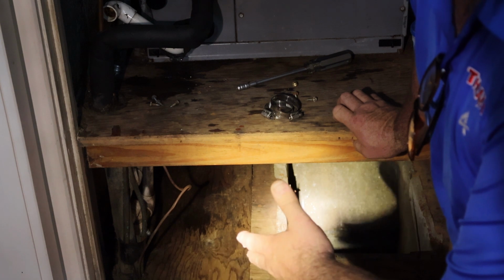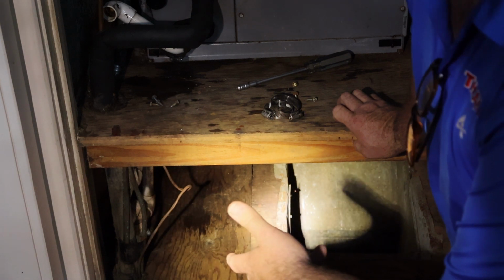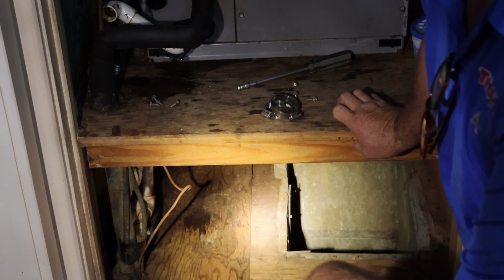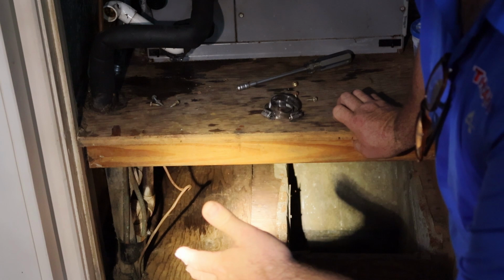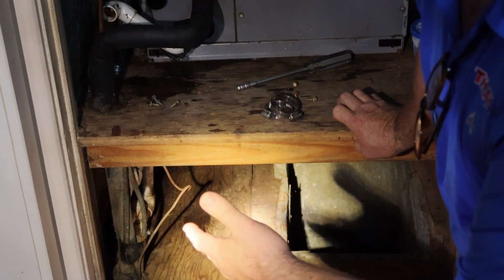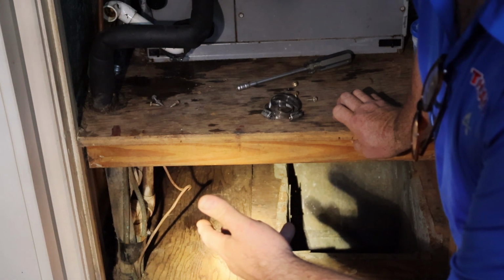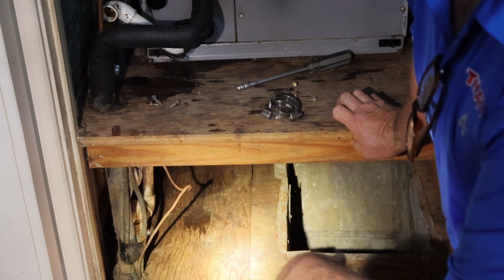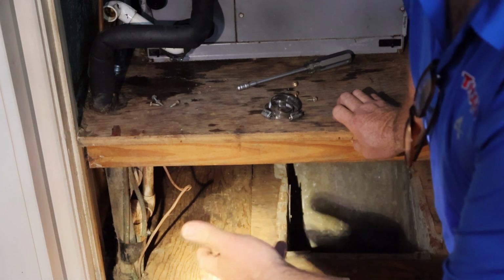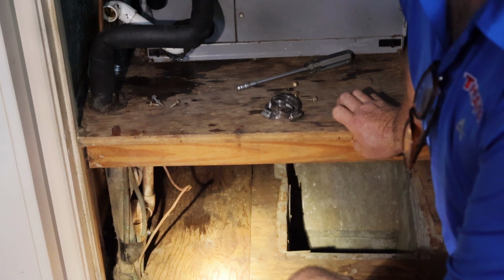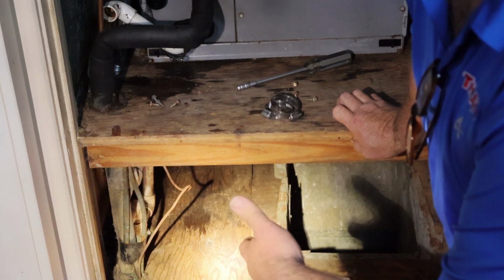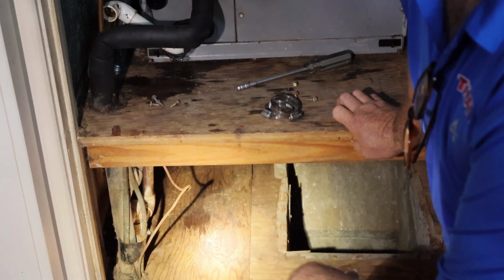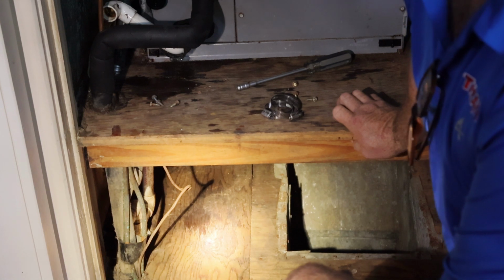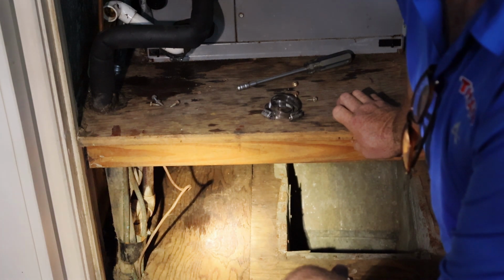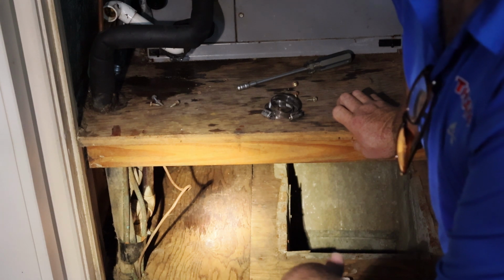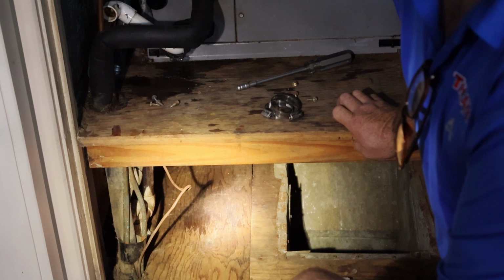You can put an inline P-trap in there. You can put a wet switch in there that, if it gets wet, just shuts the machine off. So there are options out there. But nothing is more important than making the customer aware that this condensation has to exit the home. If for any reason it can't and it backs up, it's going to the floor, and depending on when it gets caught, that determines how much damage occurs. But if they have some measures in place to prevent the machine from running when this occurs, it shuts off, can't make any more condensation, and it eliminates the damage. What they could come home and find is that the machine's not working. A technician comes out and finds that the drain's clogged. So the safety did its job.